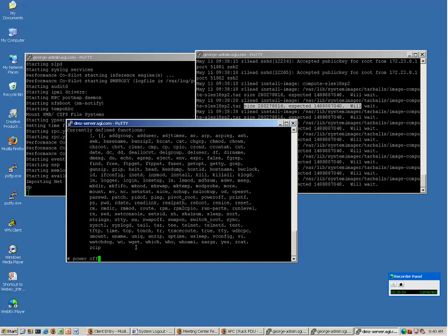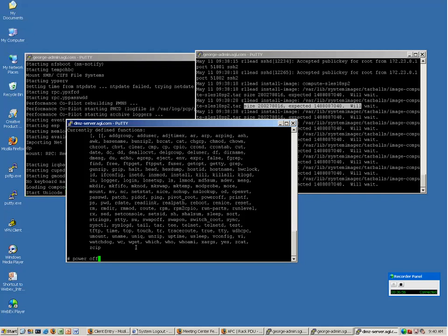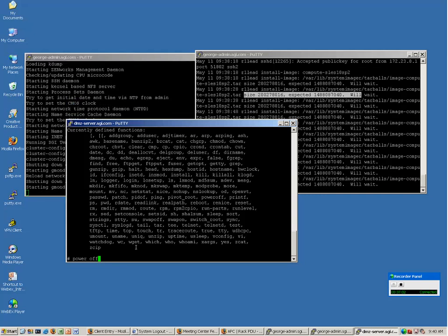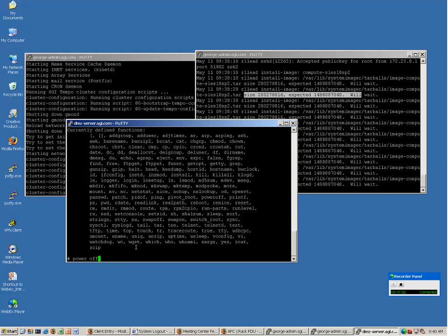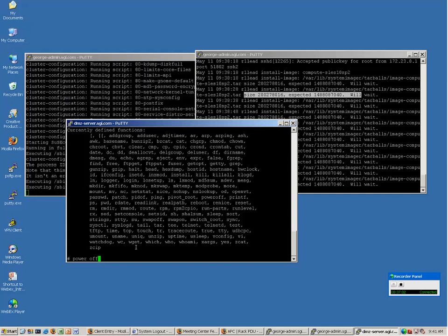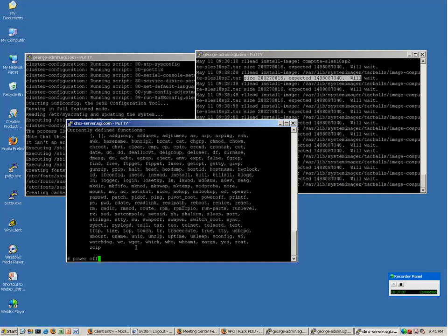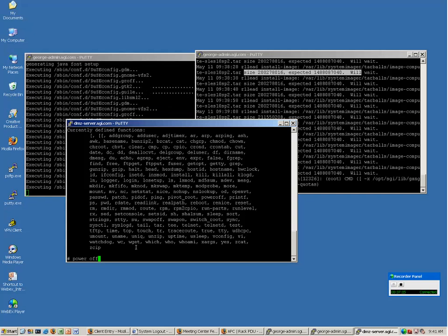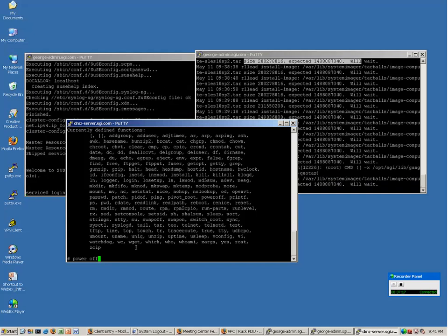If I'd been there, I might have just popped breakers. Some people don't think this is good to know, but if I did power off with no space, that would shut down the CMC itself. And remotely, I had no way of turning that back on again. Somebody would have to be physically there to pop breakers. So using power off with no space is how I actually shut down the CMC itself. But this power off is basically going to recycle the logic to the Ethernet switch. I'm suspecting it hung just because it was running a pre-release 2.1.